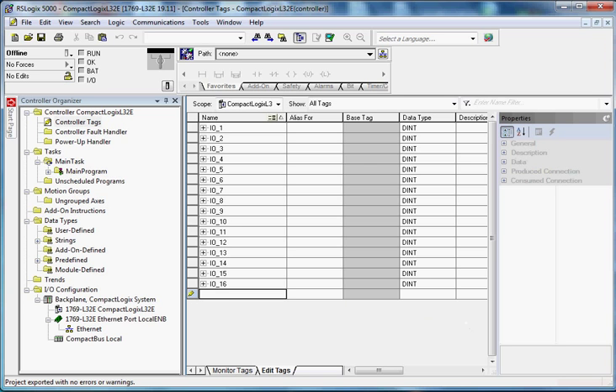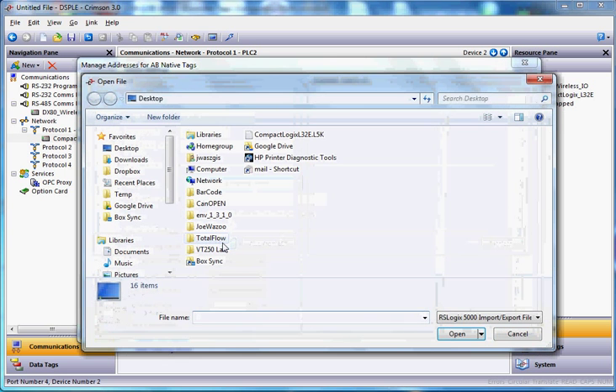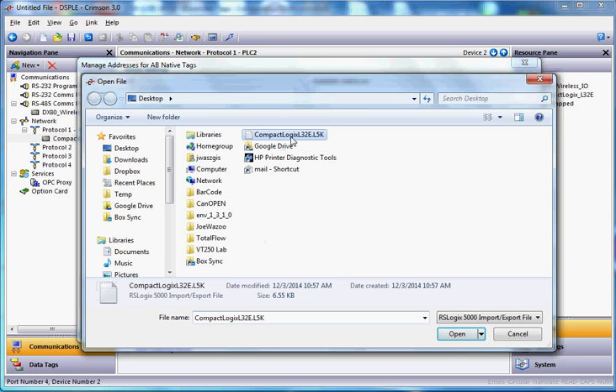Now, I'm going to go back to Crimson 3, and in Crimson 3, right here where the tag management is, I'll hit the pick button, or tag management here, and then I'll hit the import button, and I want to show you something. Here is that CompactLogix program right here, or that database. I'm going to hit open. I want you to see what happens here. Notice when it comes in, I don't see any tags. As a matter of fact, I don't see an expansion or nothing here. So what has happened is Allen Bradley has changed their software a little bit to the format is not in the correct way that our software is looking for.